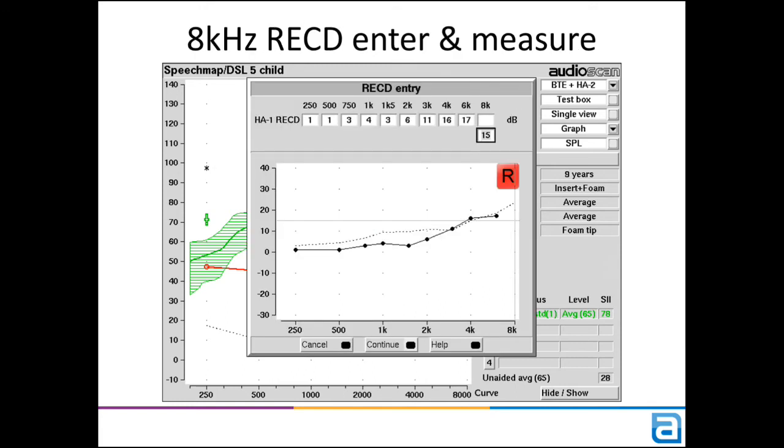Likewise, RECD on all products are measured and entered with an extra point at 8 kHz. Except, of course, the Verifit 2, which already uses wideband RECD up to 12.5 kHz.